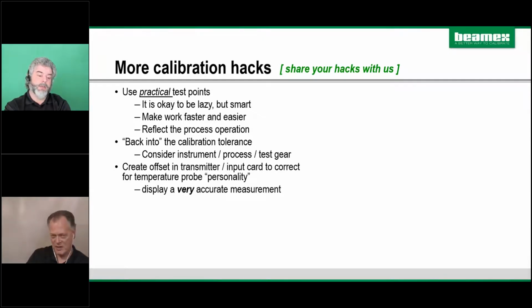So this is complicated, Roy. Can you explain this? Seriously? So if you do calibrate your loop from beginning to end, then you have an offset in the transmitter and you have an offset in the DCS card, but maybe you do the loop where you only do the intro point and the outro point. Is that a thing? So if we had done the temperature on the probe and then only recorded the display in the DCS, we could do that. And if it was a third of a degree off, we could do an offset in the DCS of a third of a degree and essentially correct that value so your DCS is right on the money. That's true. And it would be a time saver.